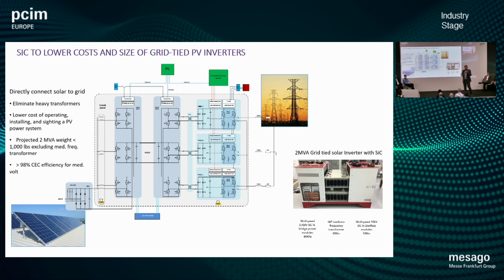Why are we so excited about increasing switching frequency? This is a 1 megawatt transformer at 10 kilohertz. 1 megawatt. If this was a silicon-based system tied to the grid, that transformer would be the size of a small car. So this is the impact of increasing switching frequency, which the silicon carbide power module brings. This example here is a PV system directly connected to the grid at 8 kV. 8 kV directly switch mode connected to the grid. This is the impact of mid-voltage silicon carbide that's available today.